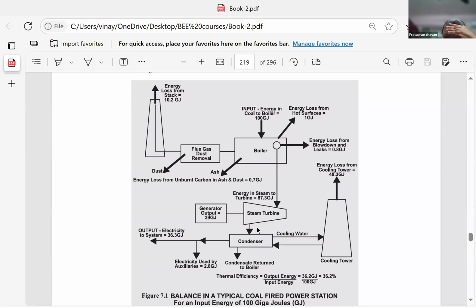So in the generator, the steam heat is partially used for rotating the generator and the remaining goes to the condenser for liquefaction of the steam back into water. This heat, which is taken out by the condenser cooling water, goes to the cooling tower. Here the temperature goes down and the heat goes to the atmosphere. A major chunk of it. See here, if 100 is the input, the heat loss to the cooling tower is about 48. Right? You got it. Almost 48 to 50% goes to the atmosphere.